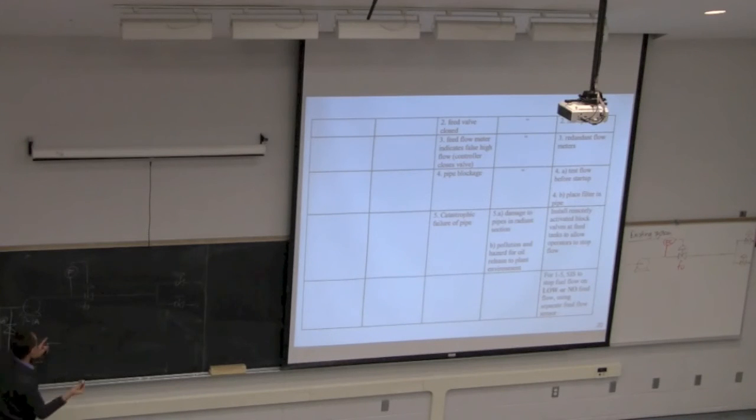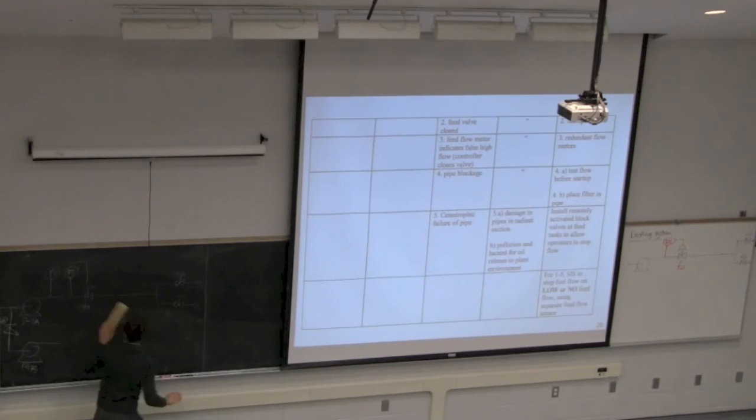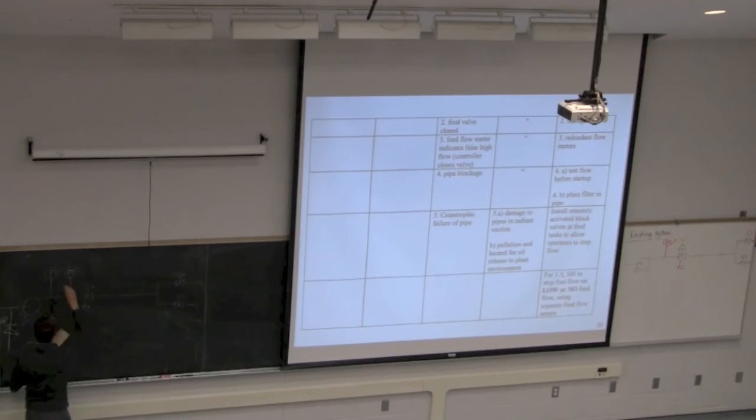Okay, so we can look at this option. Either we add the flow meter here or here. Let's take a look at it here and then we can look at it there. It can be a good discussion. So add our redundant flow meter over here. Let's call this F1 and this is F2. So redundant flow meters are added, so that we take this reading into an FY.